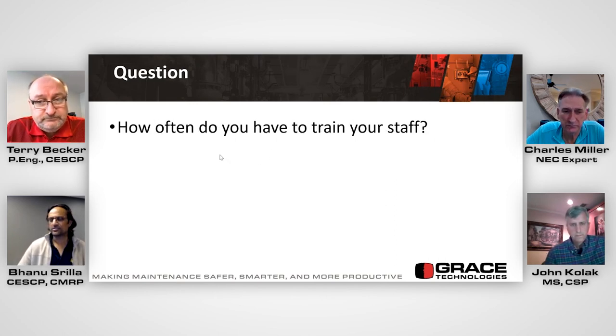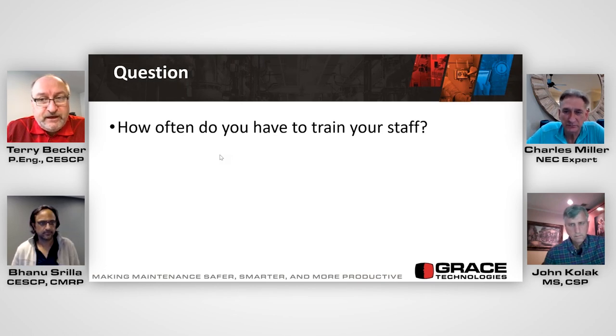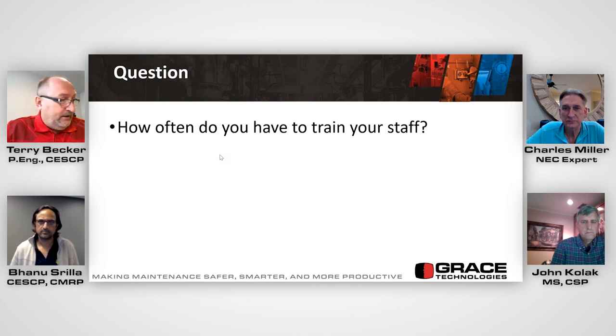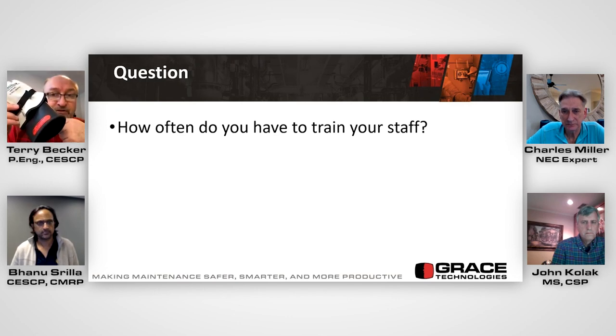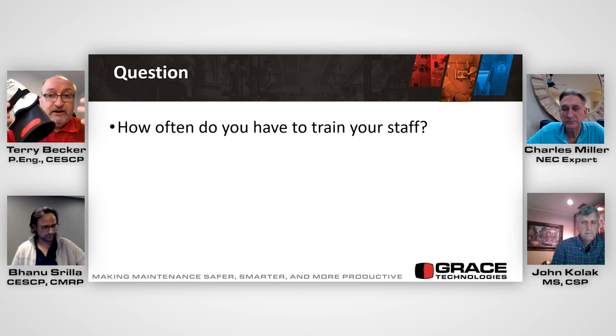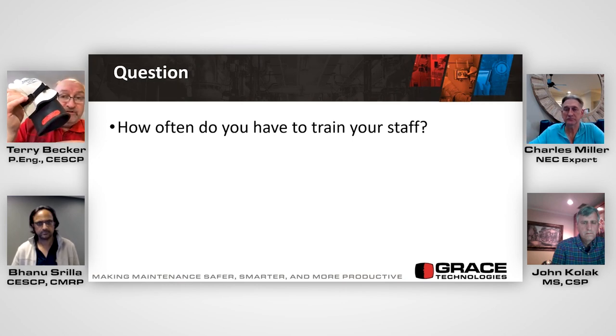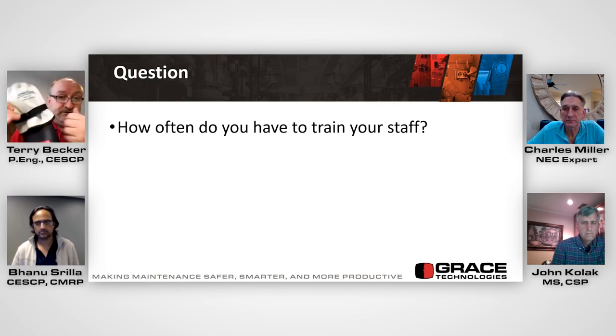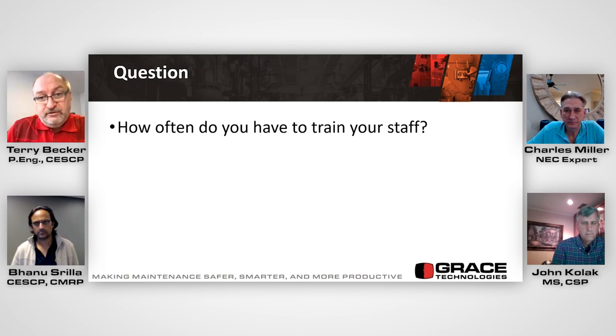How often do you have to train your staff? Training requirements are minimum 3 years, but 70E and Z462 also say that for emergencies or release of shock, you have to do that annually. So there's some caveats to the 3 years. On gloves, it's every 3 years, but I recommend a 6 month recert as a safety meeting, with a supervisor or worker volunteering for the pre-use inspection, air check, and visual. So it's minimum 3 years for generic training, 1 year for release.